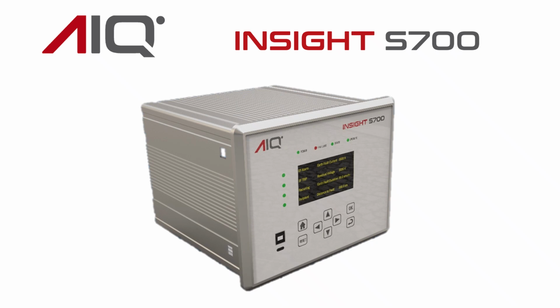Insight S700 is a high impedance earth fault protection relay installed in the distribution network's primary substation, one for each outgoing feeder. It can be set up in monitoring mode to detect earth faults including high impedance and notify the user of its occurrence. And it can also be set up in tripping mode to operate the circuit breakers to clear both earth faults and phase faults on the feeder.